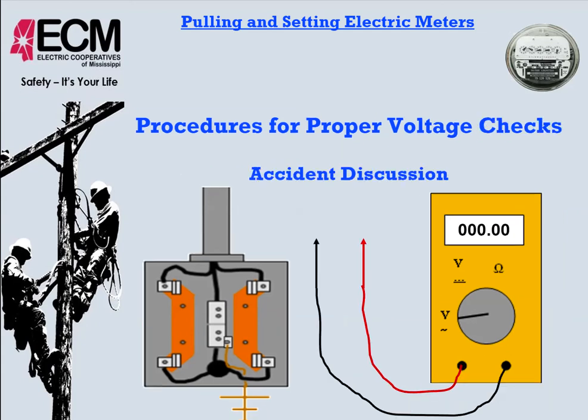Okay. There was also another incident where the proper checks were done. The voltmeter inside the meter base showed the proper voltage, but the meter did not match the voltage that was inside the meter base. It was 480, the meter was a 120/240, and it exploded. I actually have some pictures that will show.